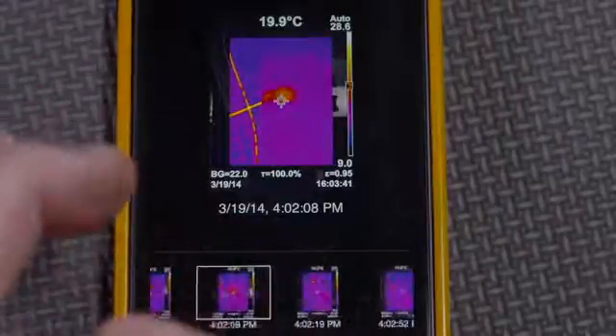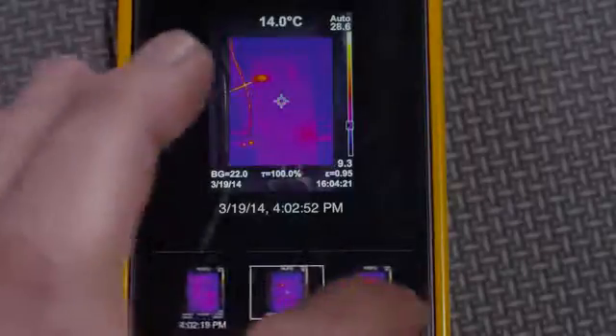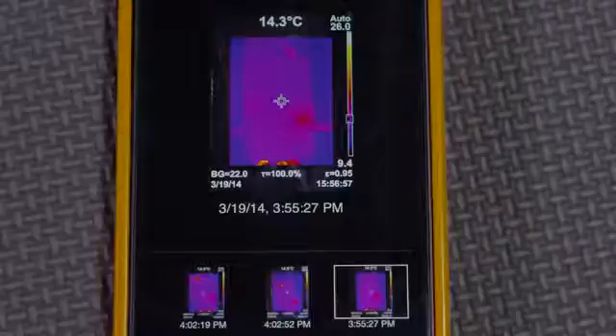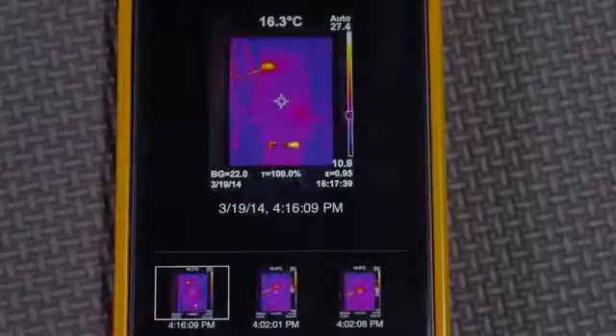By comparing the latest images to the ones taken before, maybe even a month ago, the preventive or predictive maintenance tech can determine that the circuit is getting hotter, and possibly closer to overloading, shutting down mission-critical equipment, or failure.